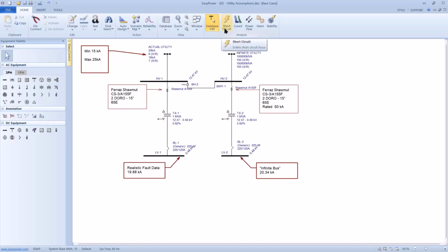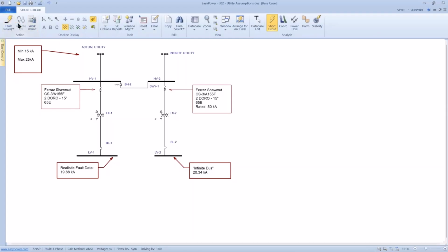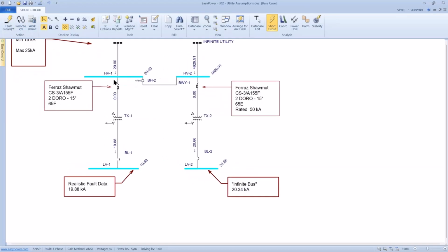But if you go into short circuit and see what the results are comparing on half cycle current, comparing the infinite source with the actual source, we see that 20,000 amps coming as the real data versus 4.6 million amps. The difference as far as my results is literally only 2 calories, or less than 2 calories, difference between reduced value and the infinite source. But if we look at the results for incident energy, we get a lower incident energy for the infinite source, and that's not being conservative.